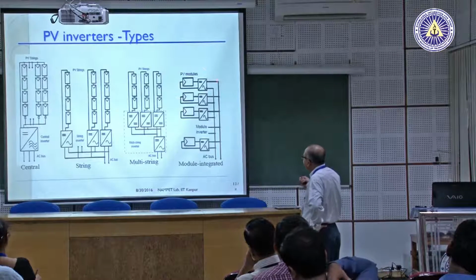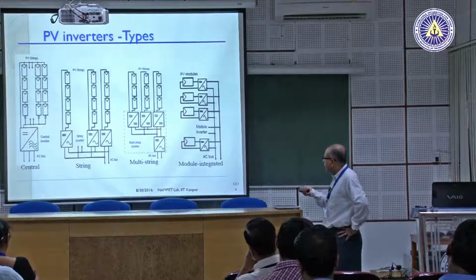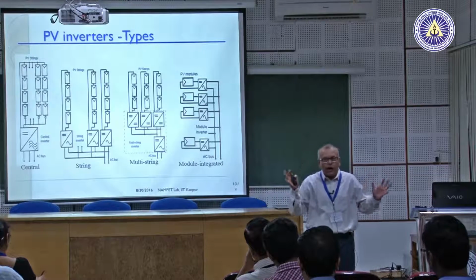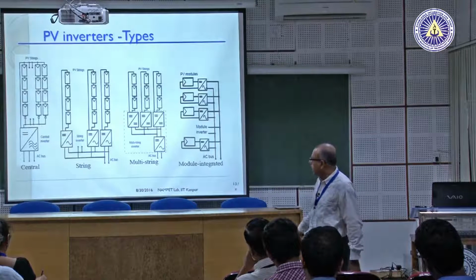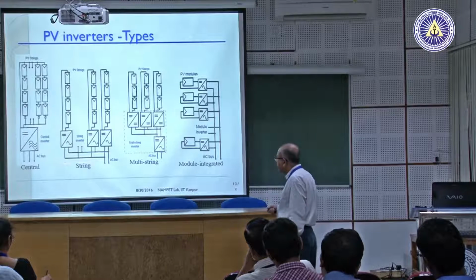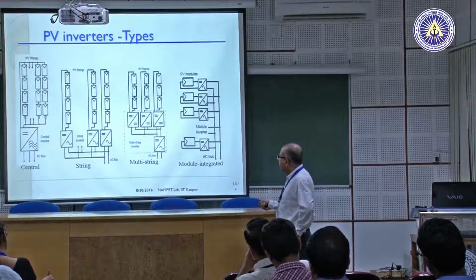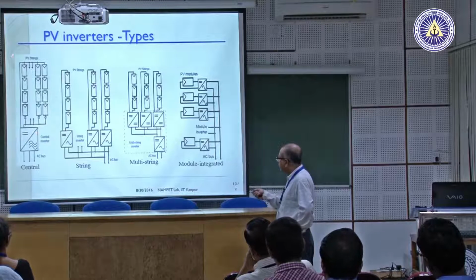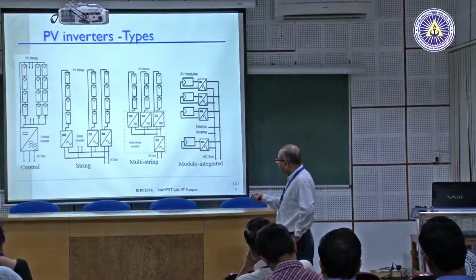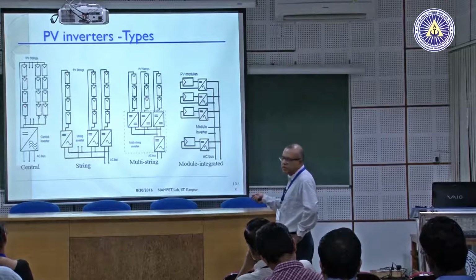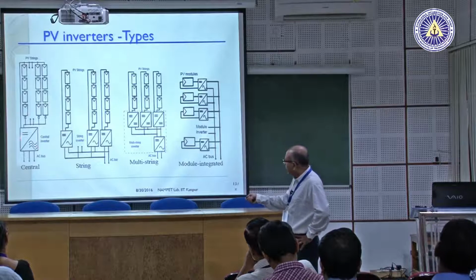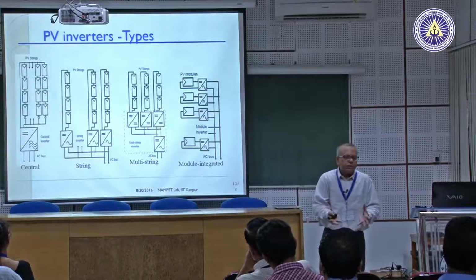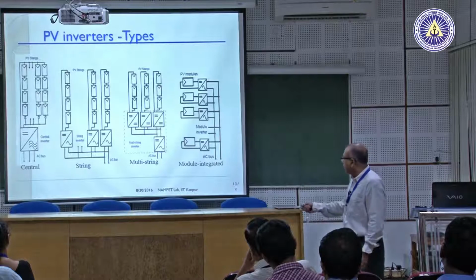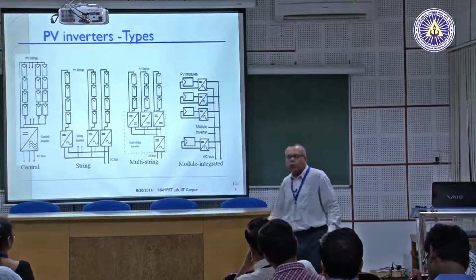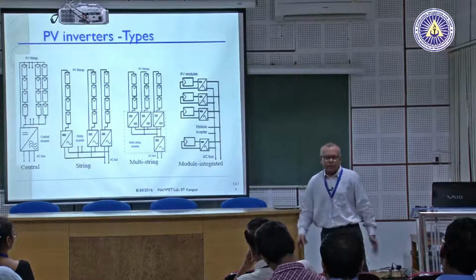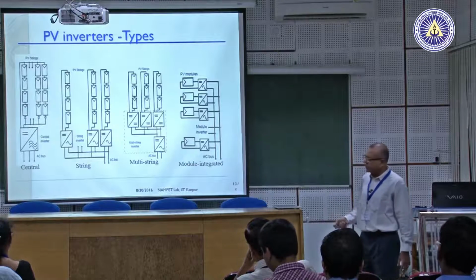There is a whole rigmarole about how one structures the entire solar PV array. This is what is called a central inverter. You have plenty of panels organized in strings, several of these strings are put in parallel, and all of them feed the DC port of an inverter, which converts it into 3-phase AC. It gives this to the utility grid, usually through a high voltage step-up transformer.